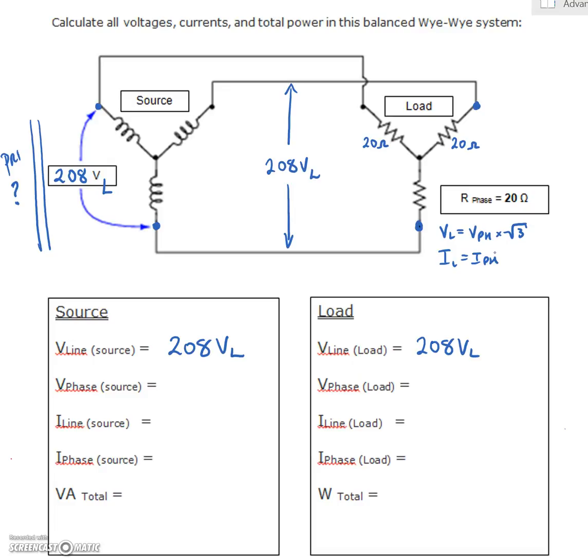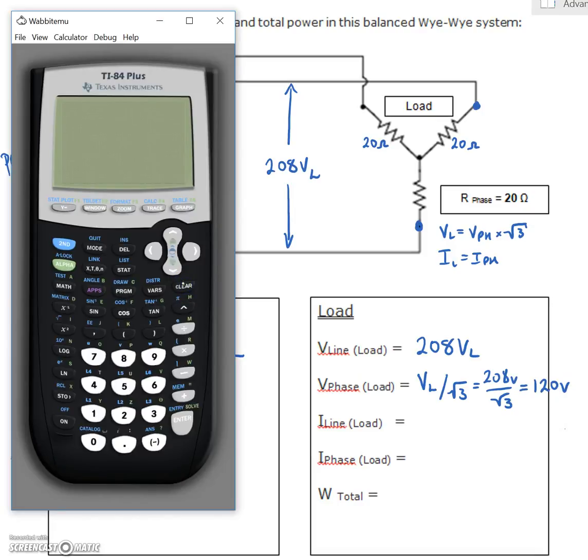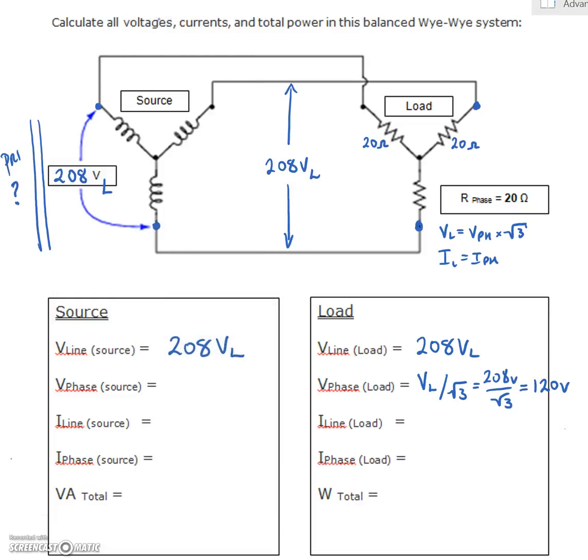So what do we need to do next? We need to find our phase voltage. Our phase voltage will be our line voltage divided by root 3. So we've got 208 volts divided by root 3, and we know that that's going to give us 120 volts. Just to confirm, we have 208 volts. We're going to divide by the square root of 3. That gives us 120 volts. Beautiful.